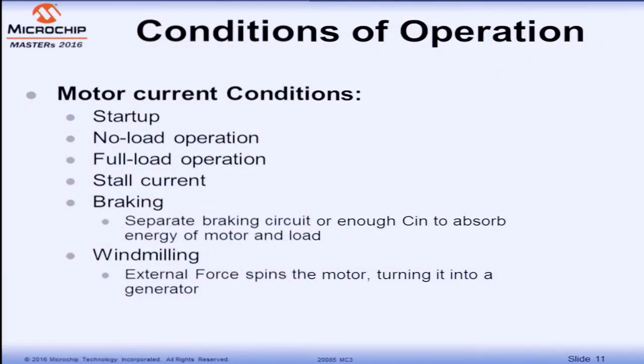With a motor, there are also different operating conditions. At startup, current will be much higher than during normal operation. No-load operation is when the motor has no load on it and it draws lower current at a given speed. Full-load operation is when the load is on the motor and it draws a bit more current, running at a slightly lower speed. Stall current is when you lock the rotor — the only impedance to current is the winding resistance. There's also braking, where you apply essentially a short circuit across the motor terminals to make it stop quickly, and windmilling, where an external force spins the motor and it acts like a generator supplying power back into your bus.